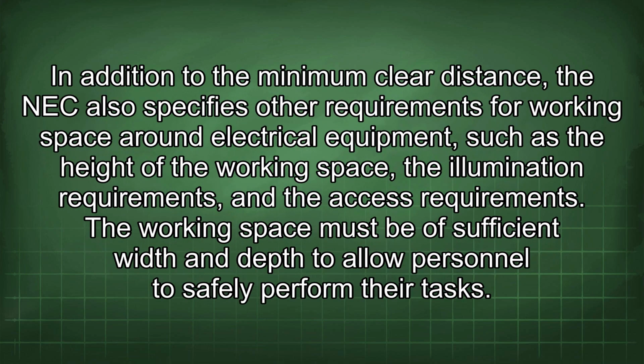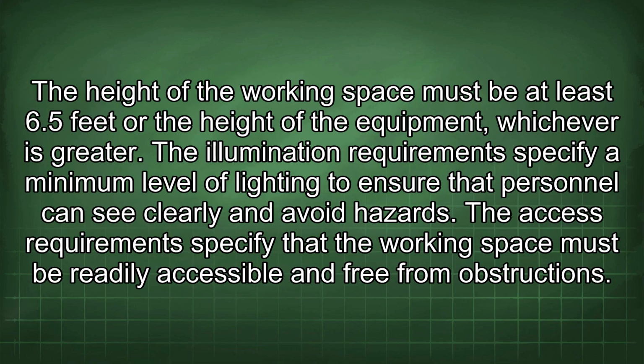In addition to the minimum clear distance, the NEC also specifies other requirements for working space around electrical equipment, such as the height of the working space, the illumination requirements, and the access requirements. The working space must be of sufficient width and depth to allow personnel to safely perform their tasks. The height of the working space must be at least 6.5 feet or the height of the equipment, whichever is greater. The illumination requirements specify a minimum level of lighting to ensure that personnel can see clearly and avoid hazards. The access requirements specify that the working space must be readily accessible and free from obstructions.